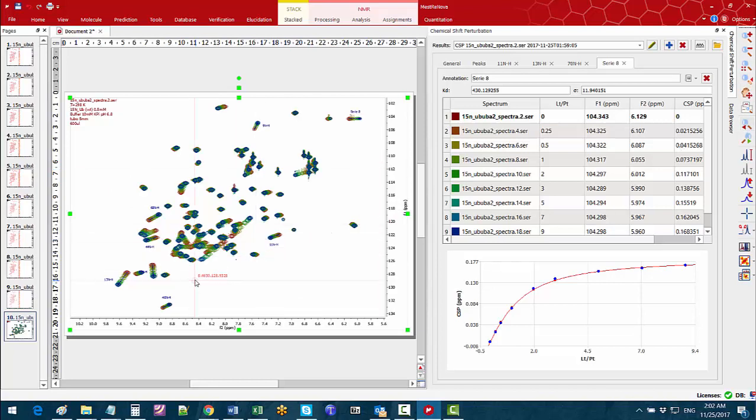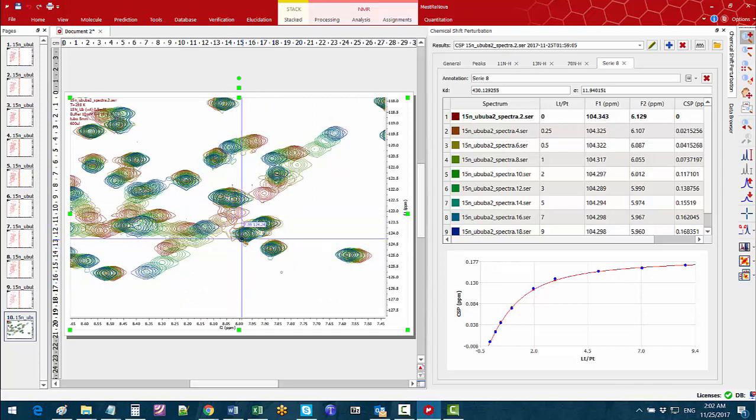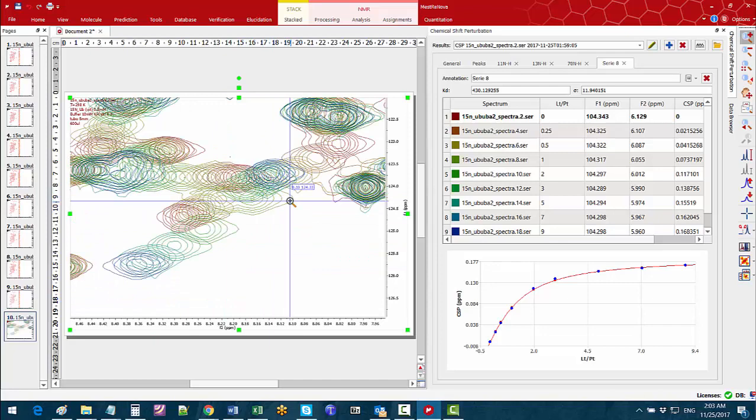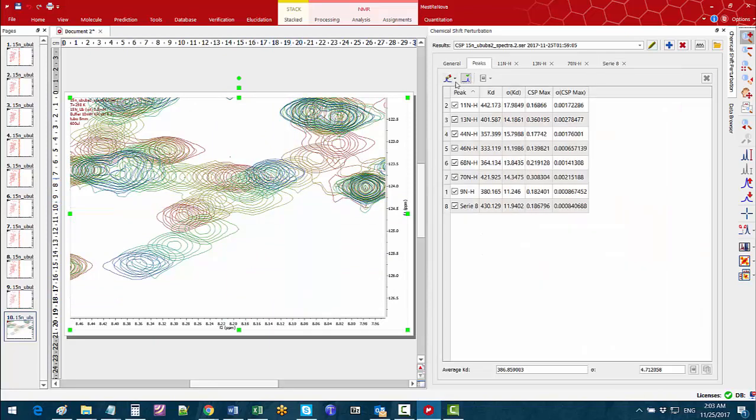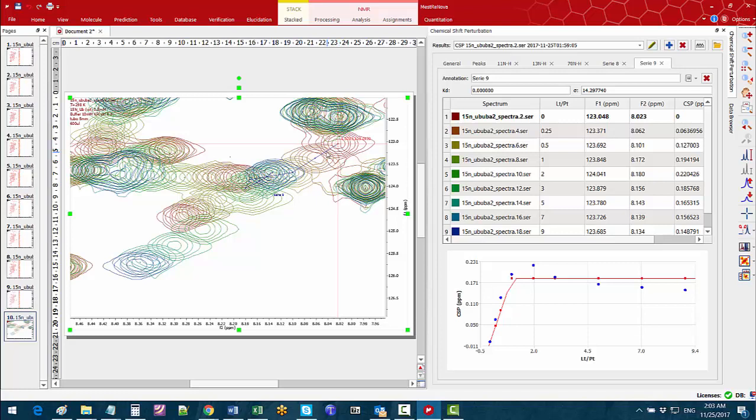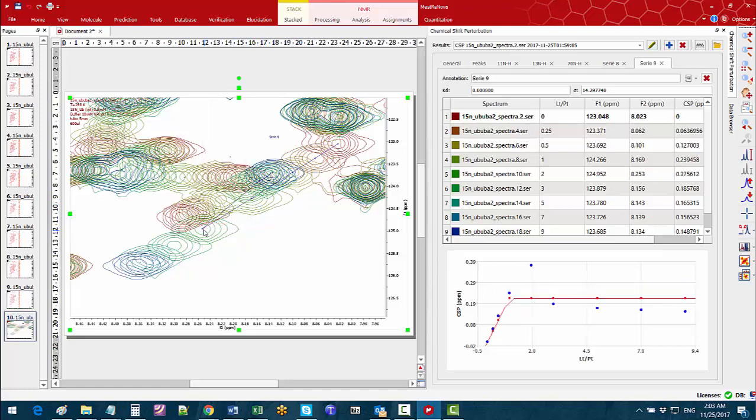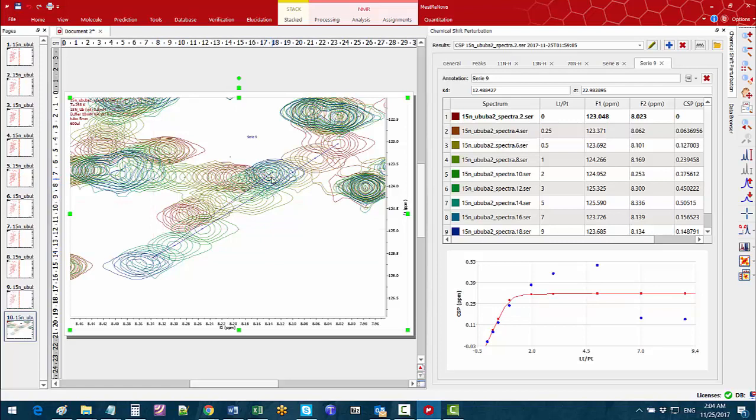If I am interested in another peak, for instance in a crowded area where automatic peak tracking is quite difficult, then we can do manual correction to adjust the automatic peak tracking results. From the peaks tab we can use the peak picking tool to select a particular peak. This peak is giving a tracking result that doesn't look right. You can see that something is wrong from the fitting results too. Manually correct the peak tracking results just by dragging this first point to the right place. In a similar fashion we can correct the next points one by one. As you can see the points on the curve on the right hand side fit much better now.